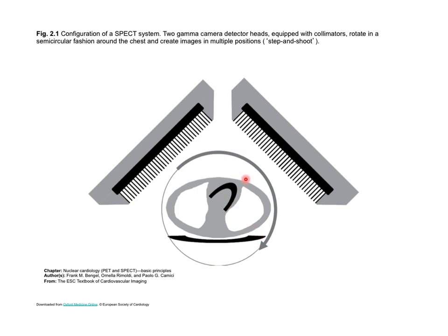Anything that comes from over here and tries to hit this detector gets absorbed by these septa. It's called an anti-scatter grid. And it sets up a geometry so that the data that I'm obtaining is primarily straight projections through the patient along straight lines. That makes the reconstruction math much easier. In fact, it makes it possible, probably.